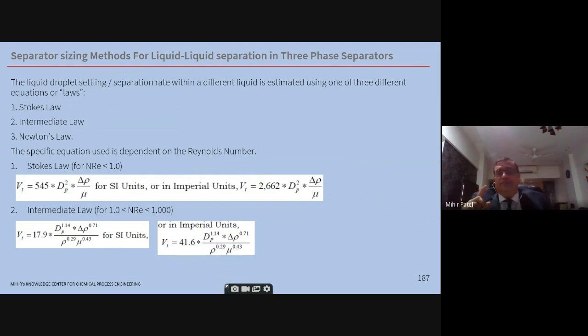For example, if you have a light liquid of very small quantity, you can go with a bucket and weir type three-phase separator, where the light liquid is collected in a bucket and then the heavy liquid overflows through a weir at the bottom. Or, for example, if the heavy liquid is of a lesser quantity, let's say water is there and the oil is of a major quantity, then you can have a boot type assembly at the bottom, because water is heavier than oil. It will collect in the boot and then it can be drained off. So there are many configurations possible.